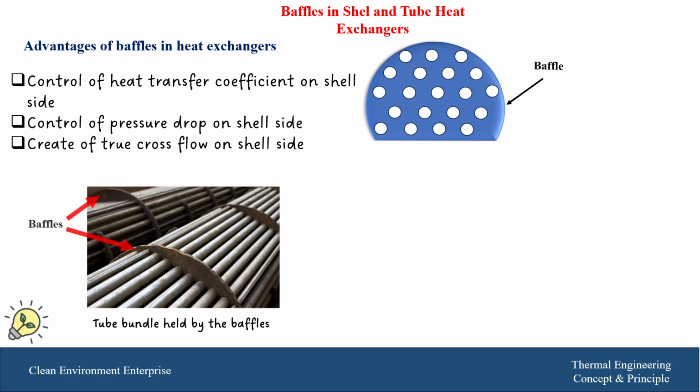The other advantage is that the presence of these baffles will create a cross flow on the shell side with the fluid that passes through the tubes.